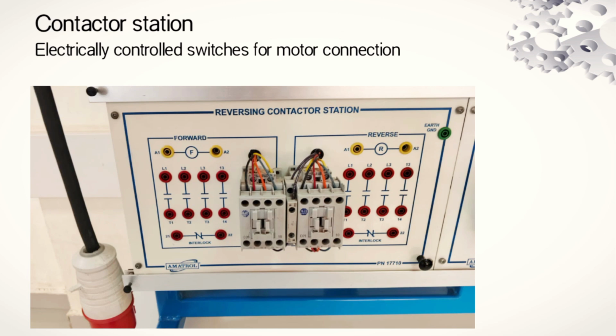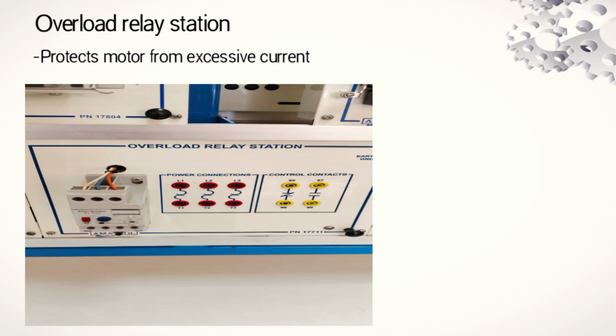Another component we have in the motor control system is the contactor station. What the contactor station does is electrically control switches for motor connections. The contactor acts like the main switch and has several switches that control the motor connection. And then we have the overload relay station. The overload relay station protects the motor from excessive current. It does this by breaking the circuit so that no current flows around the circuit. So it basically acts like a circuit breaker or a fuse.